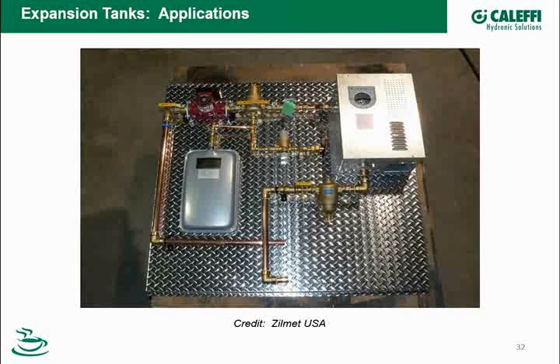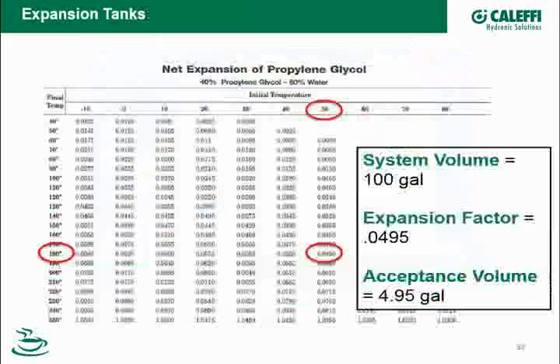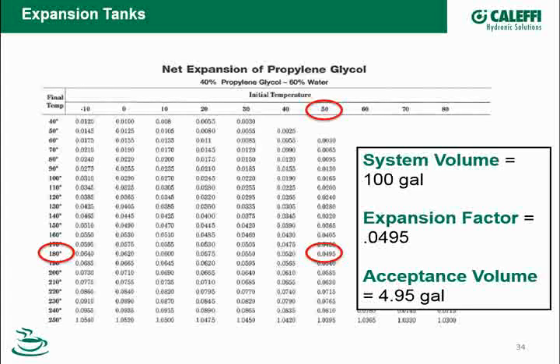Very good. Let's talk about antifreeze, polypropylene glycol. I pulled up a chart. This one's looking at a 40% polypropylene glycol mixture. I'm going under the same conditions that I pulled up on some of the old charts so we can compare the two.